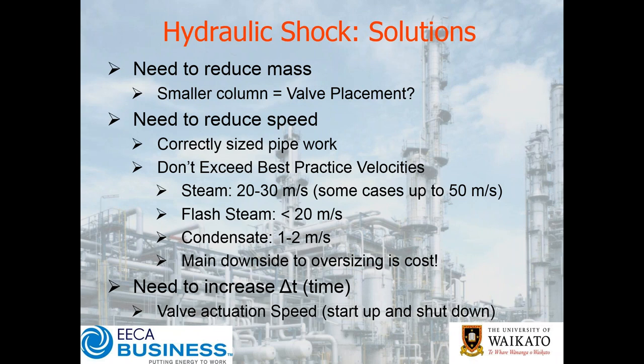Why do we want flash steam lower? Because flash steam is normally present with condensate. If we have that going too fast, it's going to pick condensate up and form a slug, which causes other problems. The only main downside to oversizing our pipe work is cost. It's very, very important to get your pipe sizing correct.